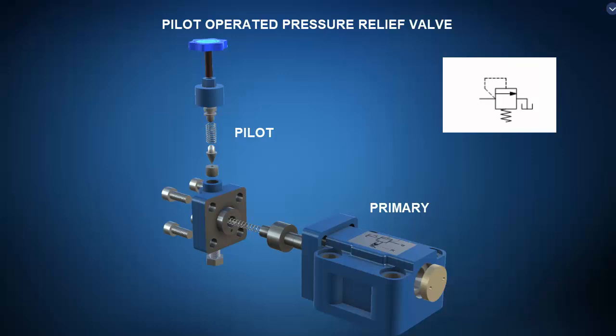If input pressure exceeds the set pressure, the pilot dart or cone is forced off its seat, upsetting the balance of the primary spool such that it opens the primary passage input to output. In this fashion, the pressure relief valve limits maximum pressure and contributes to the safe operational longevity of the larger system.